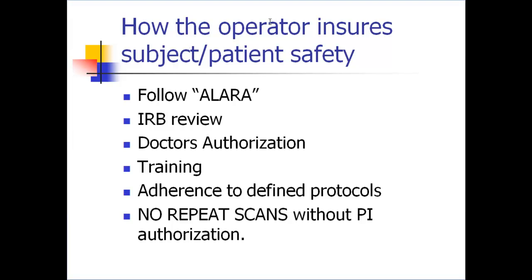So, how does the operator ensure subject and patient safety? Well, first, you follow the principle of ALARA. Second, you determine whether or not the IRB has approved the scan for this particular subject, and in this case that would be a research subject. Really foremost is to determine whether a doctor's authorization has been ordered for the DXA scan.